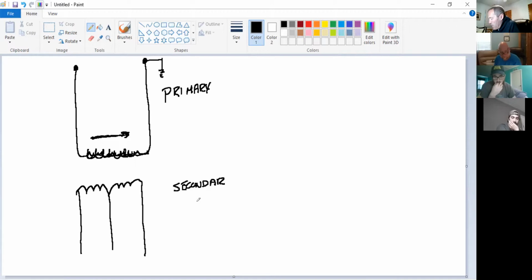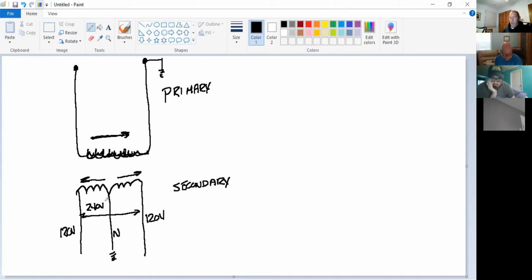How many coils do I have in my secondary? Two. One is wound in this direction, the other in this direction. I get 120 volts off of this side, 120 volts off of this side, and this is neutral, grounded. So the question reads, how is 240 volts obtained? I'm going to have 240 volts from here to here in a single phase transformer.